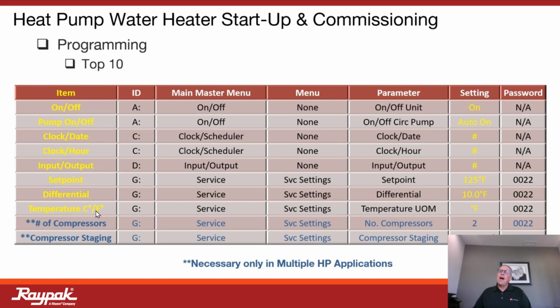So very, very easy. I would say that these top 8 right here are going to be on every job, whether it's a single unit or multiple units. If we have multiple units, the other programmable features that we're going to need to discuss is number of compressors. Maybe I have 4 units in an application, 4 heat pumps rather, or maybe I only have 2. It's going to want to know how many compressors are tied in. So this is a programmable feature that not only are we tying in our low voltage wiring, we have to go in and program the unit for how many compressors are attached in this cumulative sequence.